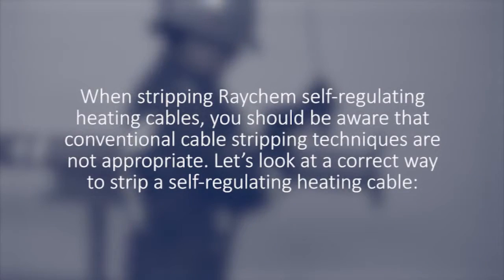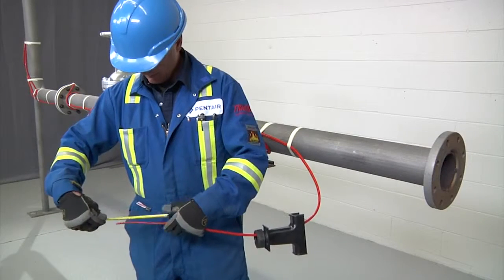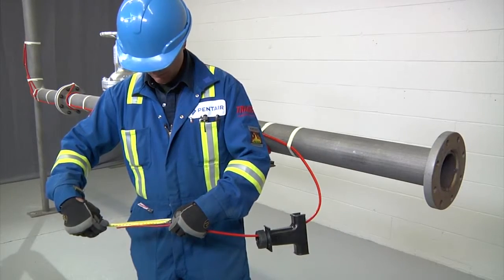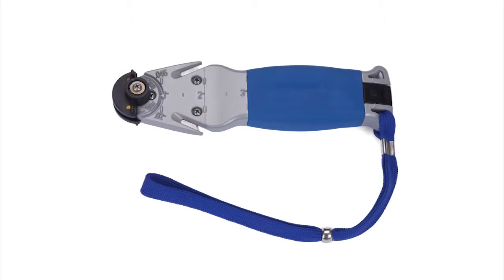When stripping Raychem self-regulating heating cables, you should be aware that conventional cable stripping techniques are not appropriate. Before stripping the cable, refer to the kit installation instructions for the exact length of each cut. Use the Raychem SR stripping tool or utility knife.